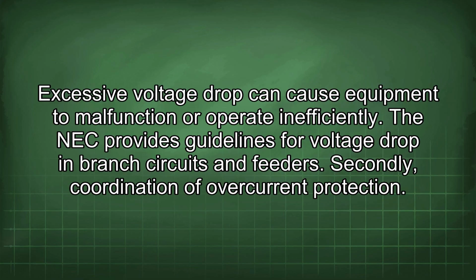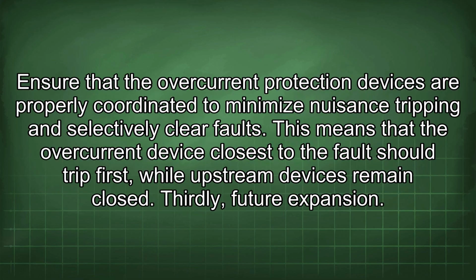Secondly, coordination of overcurrent protection. Ensure that the overcurrent protection devices are properly coordinated to minimize nuisance tripping and selectively clear faults. This means that the overcurrent device closest to the fault should trip first, while upstream devices remain closed.